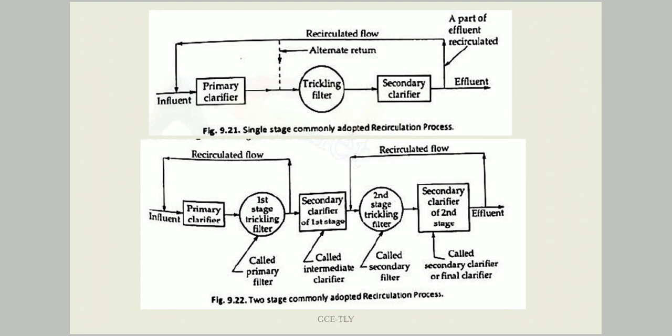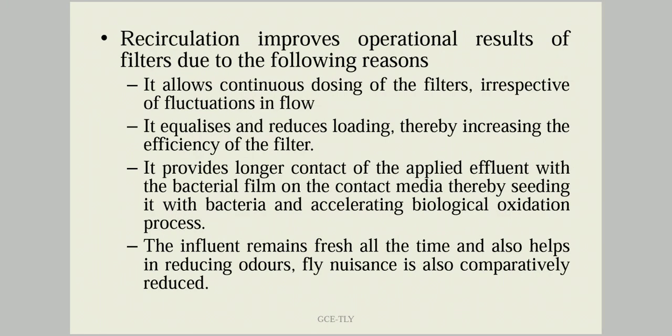After the secondary clarifier there is a second stage trickling filter followed by a second stage secondary clarifier, where recirculation is done again to the secondary trickling filter. Recirculation improves the results of the filter for several reasons: it allows continuous dosing of filters, reduces fluctuation in flow, equalizes and reduces loading, increases filter efficiency, and provides a longer contact period between bacteria and the effluent water, increasing biological oxidation. Recirculation also keeps the influent fresh and helps reduce odor compared to processes without recirculation.